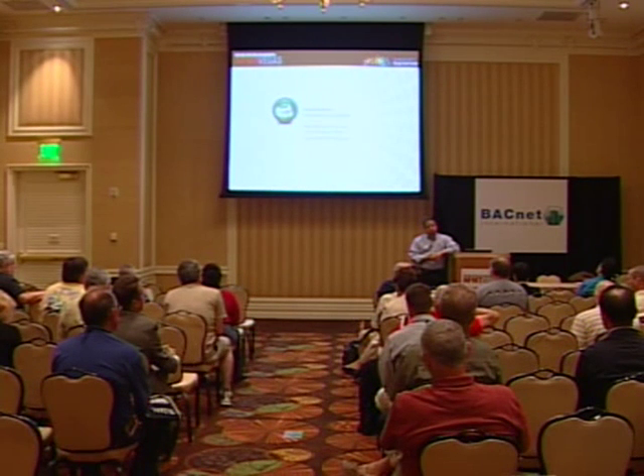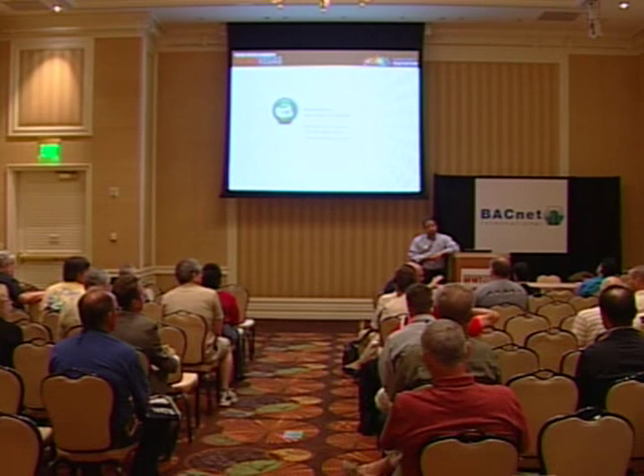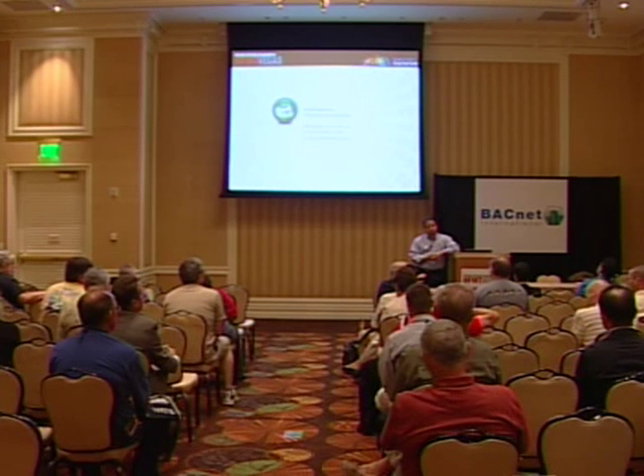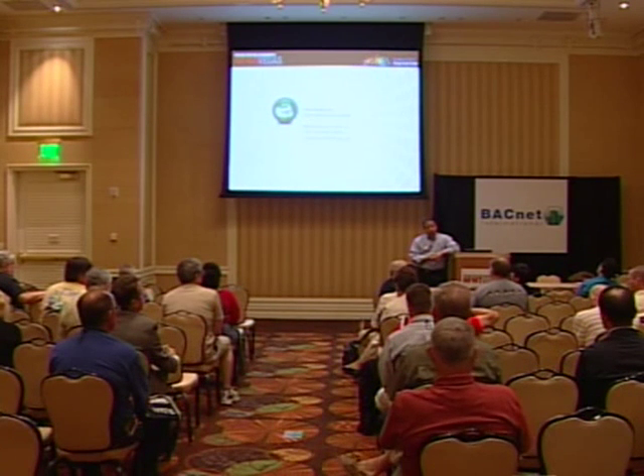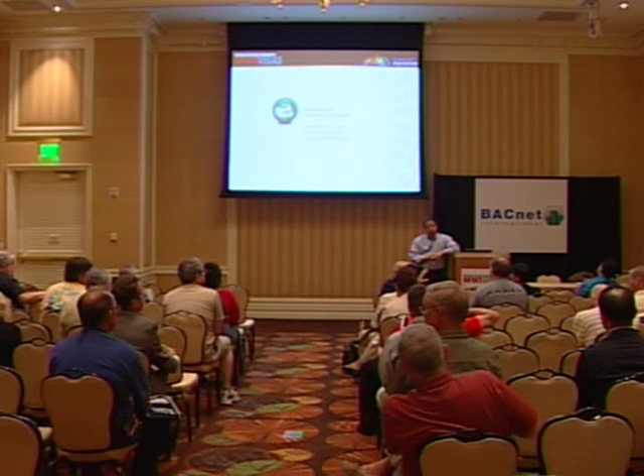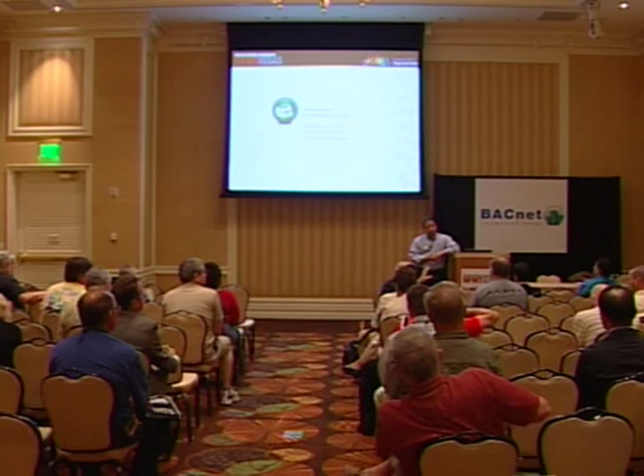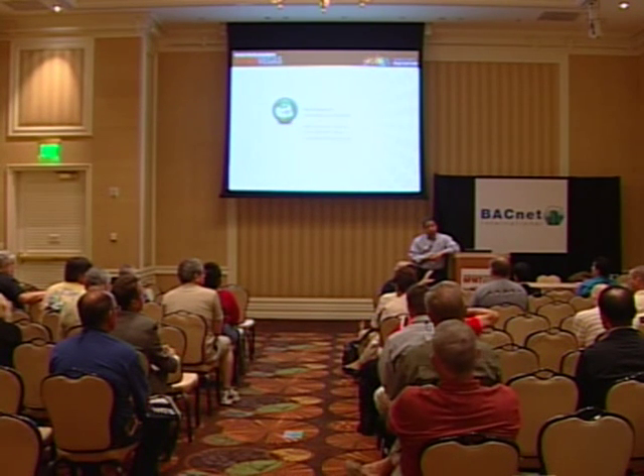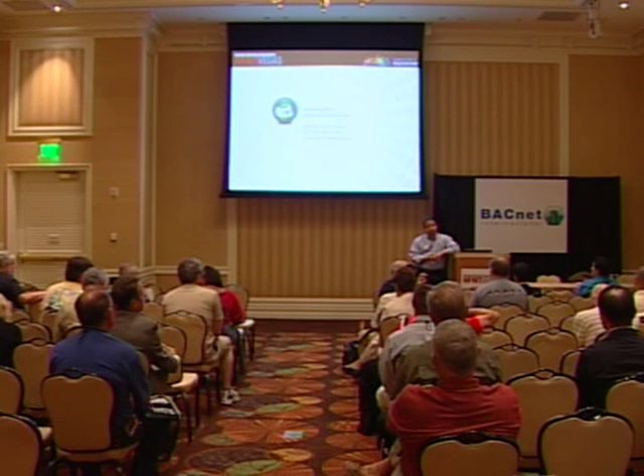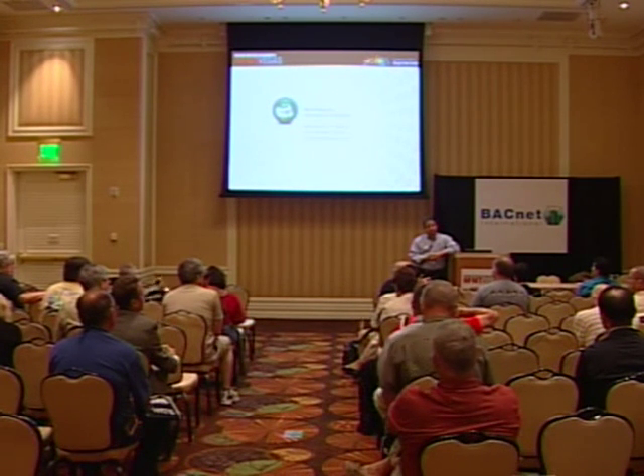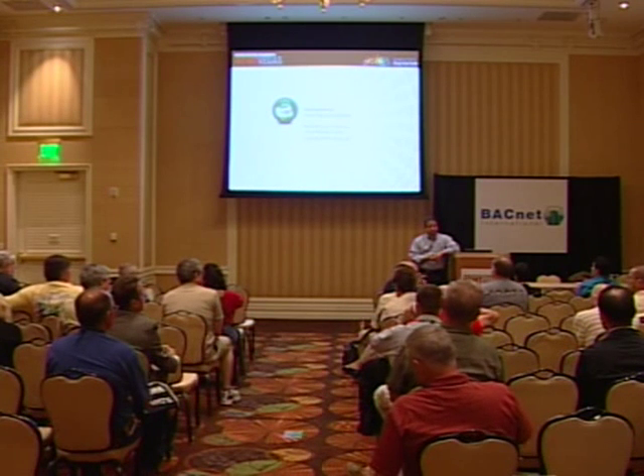One consideration you have to appreciate is that there's vanilla DALI, based on the standard, but some manufacturers, for good reasons, have extended DALI into an upgraded version. If you have a manufacturer with that technology, and we put systems in like that, you have to realize that you must buy the ballast from that manufacturer. So it's not really pitched as an interoperable standard once it's beyond the vanilla version of DALI.